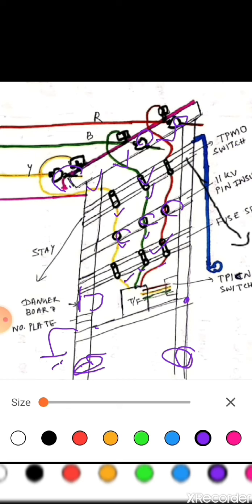Next is fabrication of some parts such as clamps. So we need to fabricate all the parts with the pole. So fabrication is required. This is the transformer of 50 kVA, 11 by 0.4 kV, that is one number is required. Here is the TPICN main switch, that is the quantity one number is required. And earthing for the pole, again the transformer will be earthed, so quantity one number. And lightning arrestor, that is 3 numbers of lightning arrestor will be required.